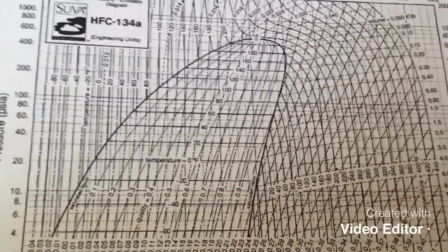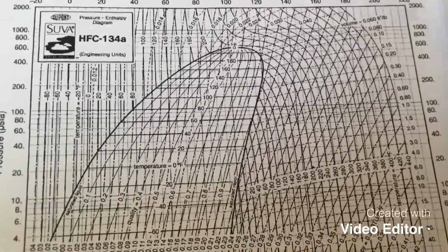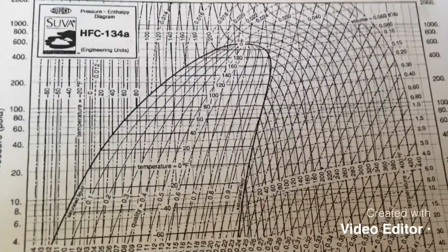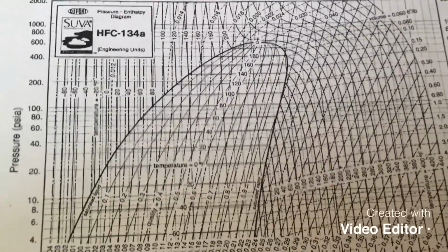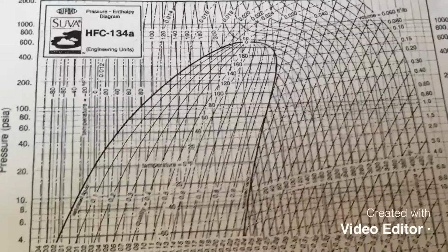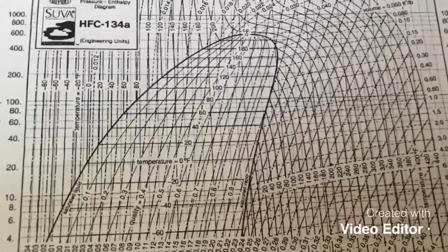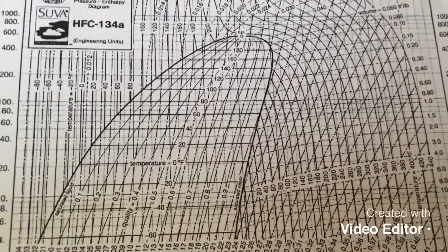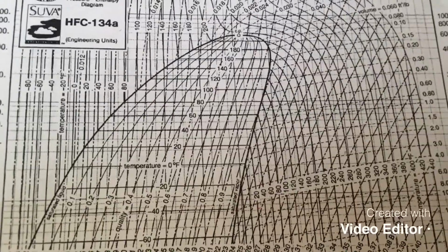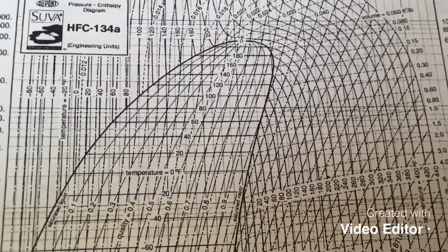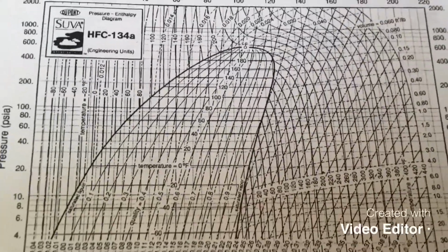Okay. I don't want you to create your own pH diagram. Just use this diagram and use a color pen to put your 4 points there. Okay. And then you will see the pH diagram. Then you will clearly see the degree of superheat at the evaporator outlet. Compare the actually measured point in the vapor region to the ideal point on the line. Okay, so that's the degree of superheat. Okay, so that's the report requirement for lab 1.